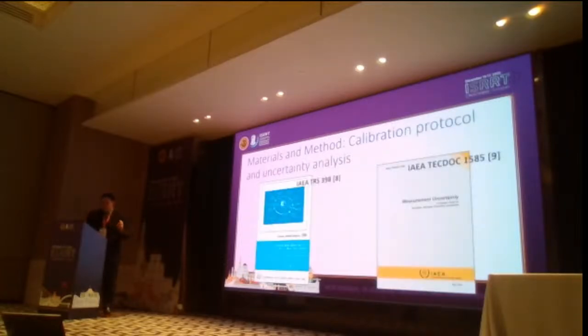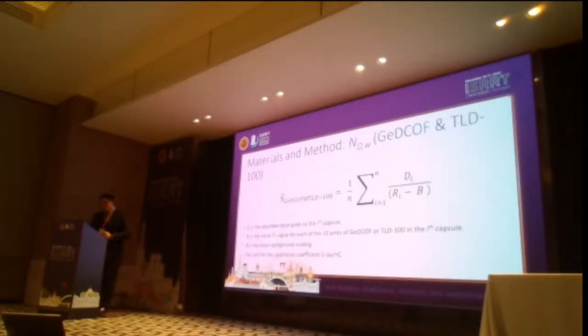So in terms of the calibration protocol, we are using the technical report series TRS 398 by the IAEA. And for the measurement of uncertainty, we are using the guideline by the technical document 1585. So we will produce a calibration coefficient, the symbol N, for each type of dosimeter, the GeDCOF and also in comparison to the TLD. And then the equation for the calibration coefficient determination is as follows.